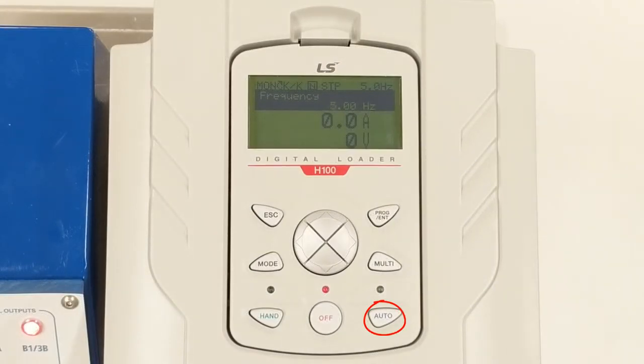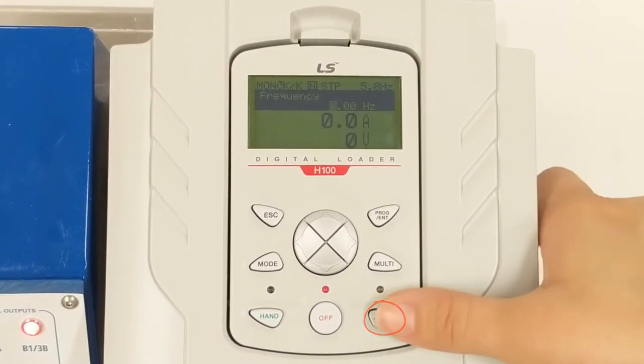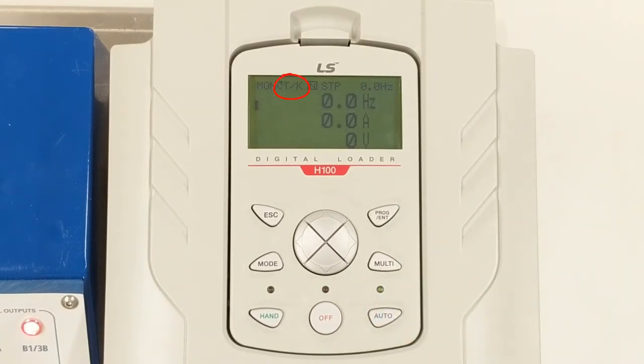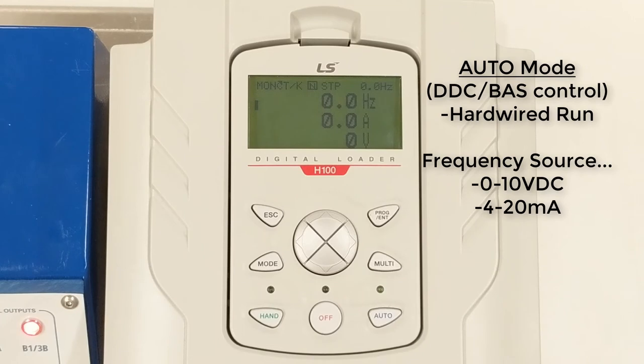Now let's talk about the auto mode. When you press the auto key, by default you should see TK on the top of the display. This means terminal start command and keypad frequency reference. Auto mode typically refers to controls from an automated system such as a DDC or a BAS. Let's look at how you would program the VFD to look at a hardwired run command and a 0 to 10 voltage source for speed control.